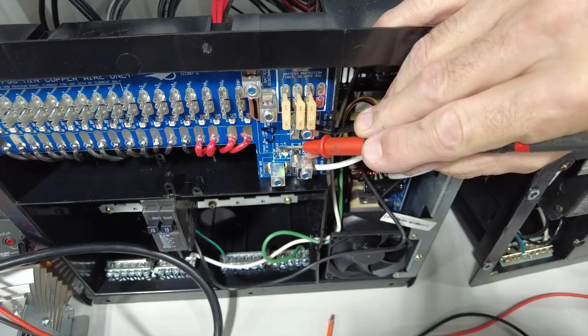While we're looking at this, I also want to point out that right down here on this circuit board is a dip switch, and this power converter comes preset for lead acid batteries. But if you slide this dip switch over to the Li port for lithium and look at the output, you'll see it just went up to 14.5, 14.4. If I move that back over to lead acid, you'll see it went back to 13.6.